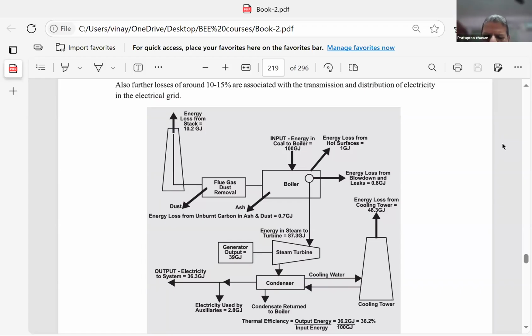That means heat gainfully utilized in the numerator divided by the heat generated by fuel burning—the ratio gives you efficiency. In only electrical operation, the electrical generation equivalent of heat is only 30%, and total heat is at the bottom, so efficiency is 30%. But if I can use 80-85% of the heat generated by the fuel, then the numerator will be greater while the denominator remains the same, because the same fuel is used. There is an efficiency improvement.